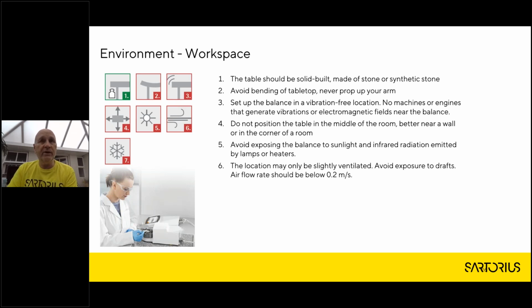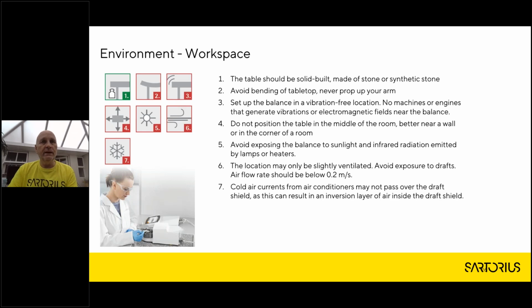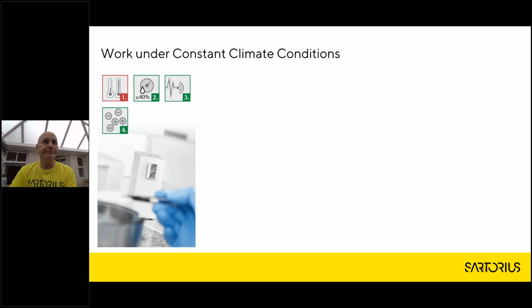Avoid airflow, so the airflow rate should really be less than 0.2 meters per second if possible. If there's an air conditioner in the laboratory, position the balance in the opposite section of the laboratory to the air conditioning, so that it doesn't have any effect or has minimal effect on your balance and your weighing process. If you can, control the laboratory environment and create constant environmental and ambient conditions within your laboratory.